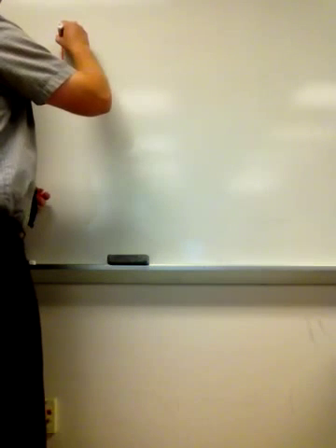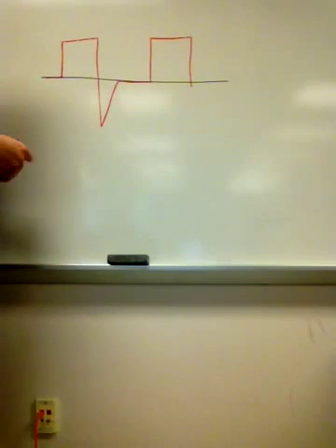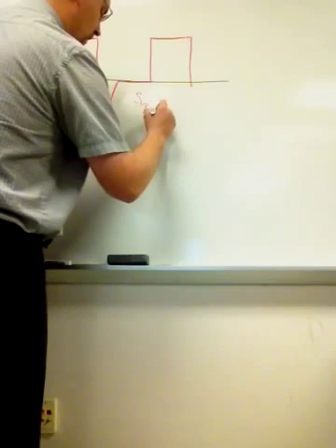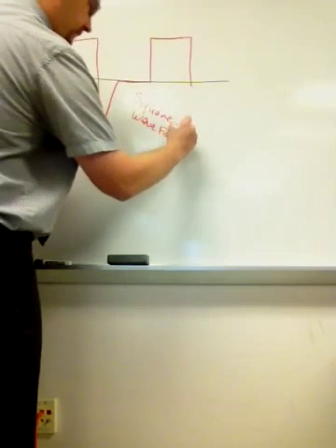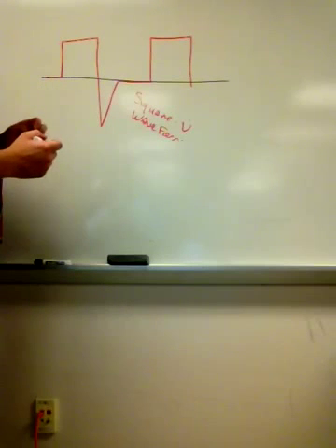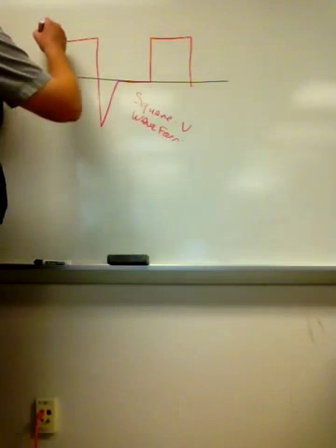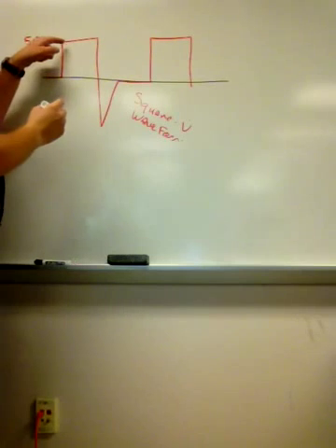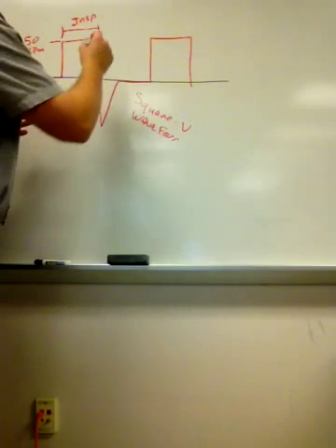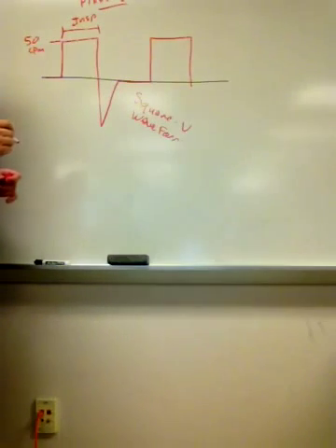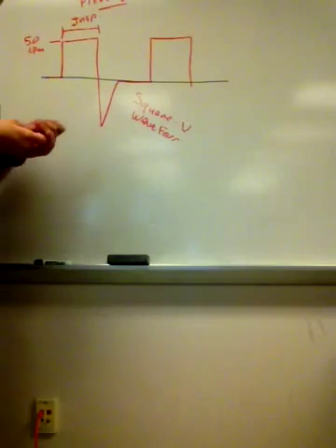Now let's talk about the basic look of the waveform. What I drew you earlier was something that looked kind of like this. That's what's known as a square waveform, a square flow waveform. And what this means is I get to my peak flow, whatever that peak flow is, we'll say it's 50 liters per minute here. And I maintain peak flow, that 50 liters per minute, throughout the entire inspiratory phase. So I have a fixed flow, it doesn't change.